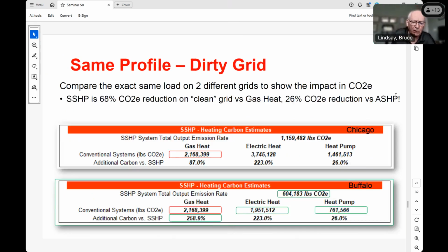I should have shown this a little earlier, but we're looking at two different electric grids. We're looking at the grid in Chicago, we're looking at the grid in Buffalo. Okay, Chicago is a pretty dirty grid. Buffalo, it's almost all hydro and nuclear, very clean. If I rip out a gas boiler and put in an electric boiler, I actually increase the greenhouse gas emissions by almost a factor of 2. People don't realize that that can happen. You go down to Buffalo, and we rip out the gas heat, put electric heat, it stays the same. Have you decarbonized? Not really. If you go to a heat pump, significant reductions, okay, on both, but there's still a lot of greenhouse gas going off. If you use a storage source heat pump, we can actually obtain an additional 26% savings in the greenhouse gas. We get down to, we basically cut it in half. Next slide.